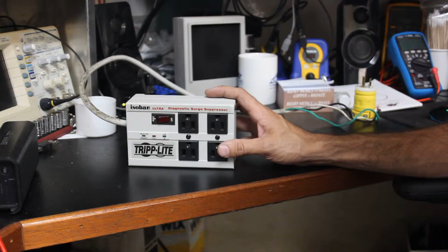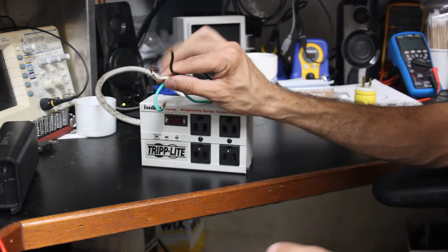It turned out to be this bad surge protector, and it took me a while to actually troubleshoot this issue. I'm going to hack a plug onto the end of this. It was removed directly from a machine that was wired in through a DIN rail termination, so whenever they make the machine, they cut the plug off and all that. I'll put another one on, plug it in, and take a closer look at why it was so hard for me to find this problem. Hopefully it'll duplicate the issue on the bench.